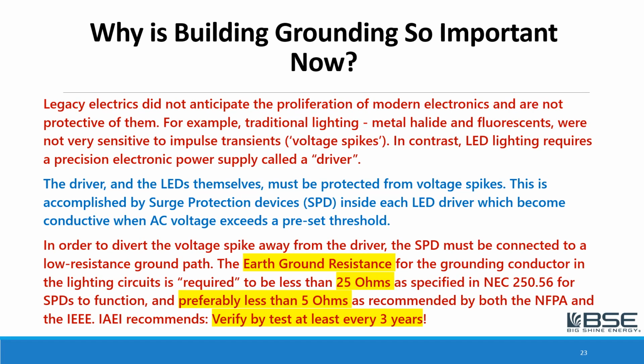By the way, the Institute or International Agency of Electrical Inspectors recommends that you test your system at least once every 3 years. This is the loophole I wanted to mention. In the National Electrical Code, and I think this is true even in the latest versions of the code, they had a provision that if you put in a driven rod grounding system and you measure the resistance, it should be less than 25 ohms.